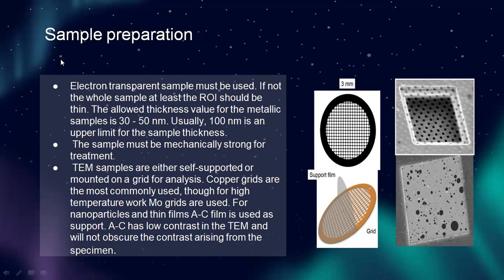Next, I will discuss sample preparation for transmission electron microscope. Electron-transparent samples must be used; if not the whole sample, at least the region of interest should be thin. The allowed thickness for metallic samples is 30 to 50 nanometers. Usually 100 nanometers is an upper limit for sample thickness. The sample must be mechanically strong for treatment. TEM samples are either self-supported or mounted on a grid for analysis. Copper grids are most commonly used; for high temperature work, Mo grids are used. For nanoparticles and thin films, an amorphous carbon film is used as support due to its low contrast in TEM, so it will not obscure the contrast arising from the specimen.